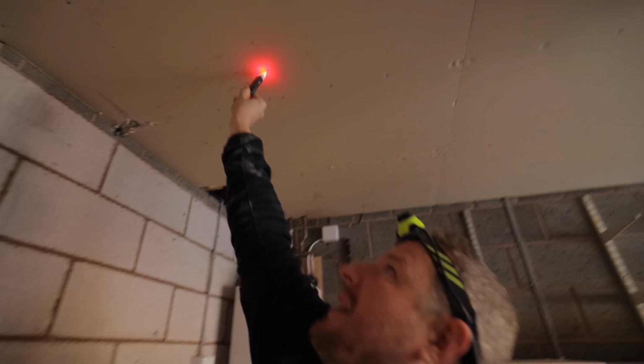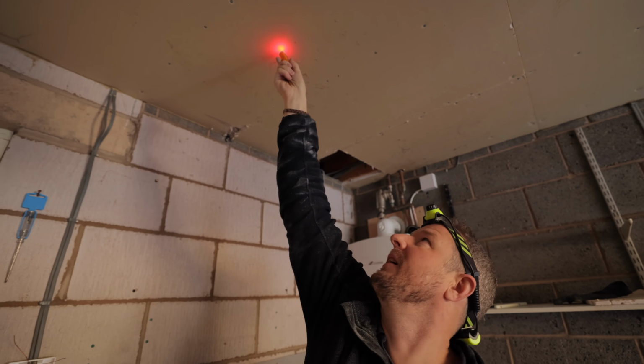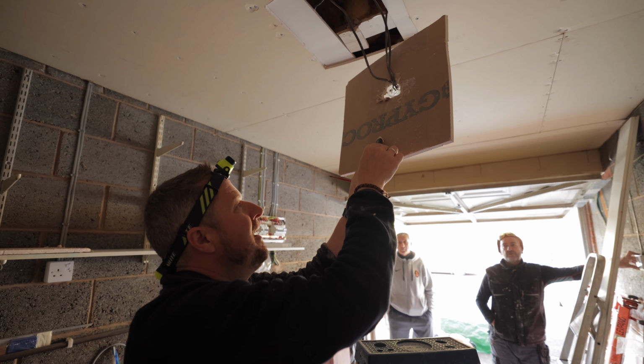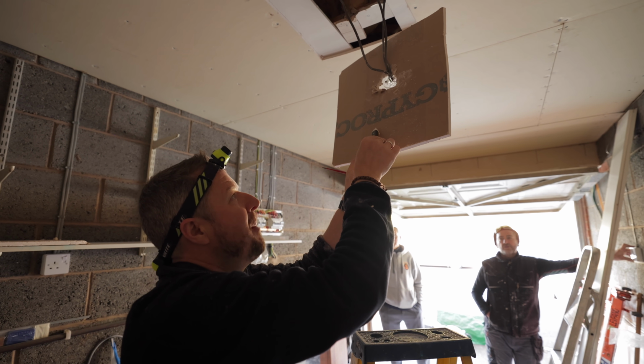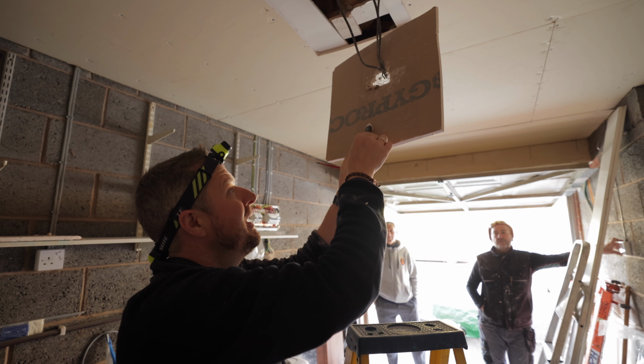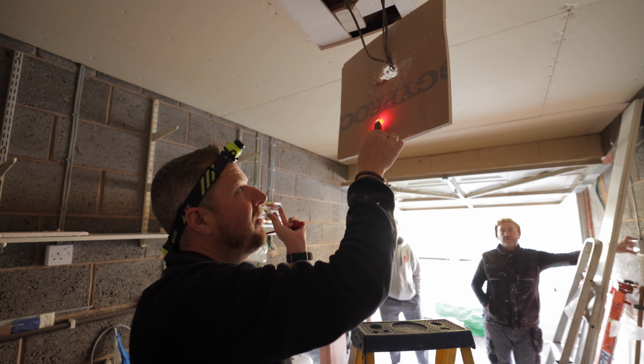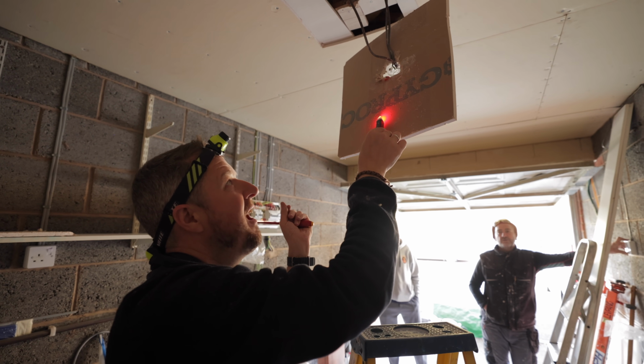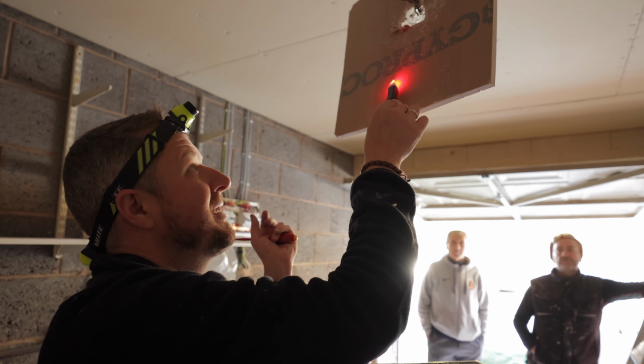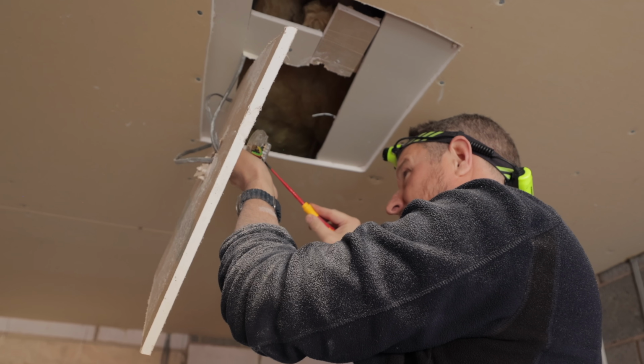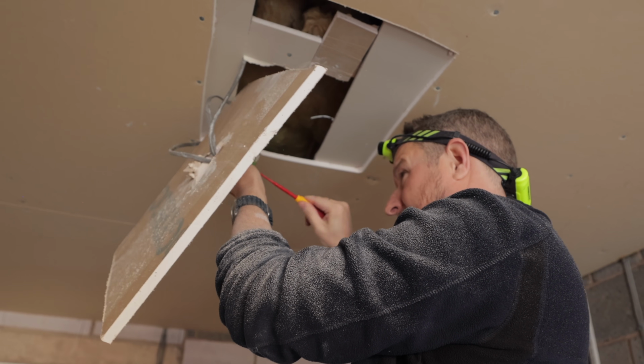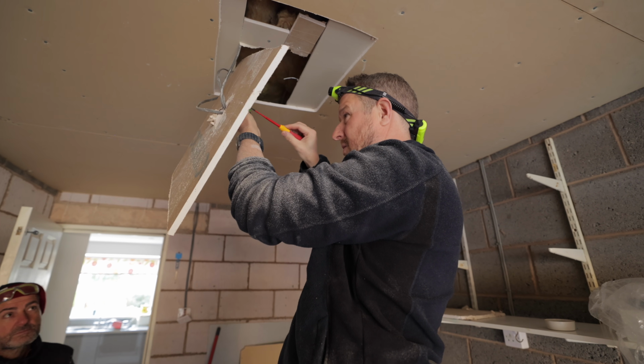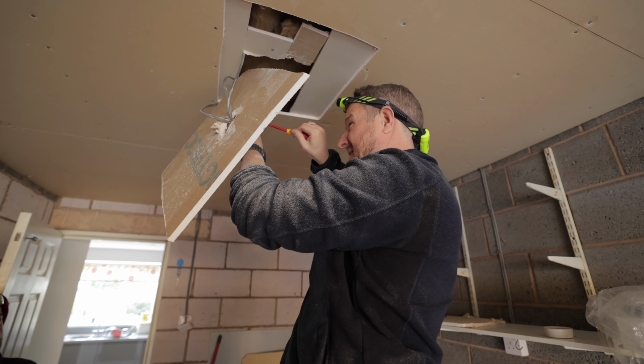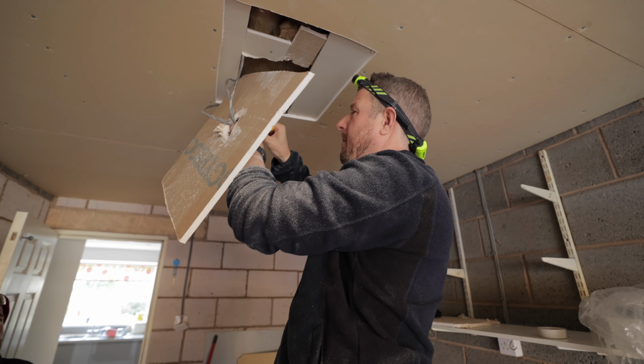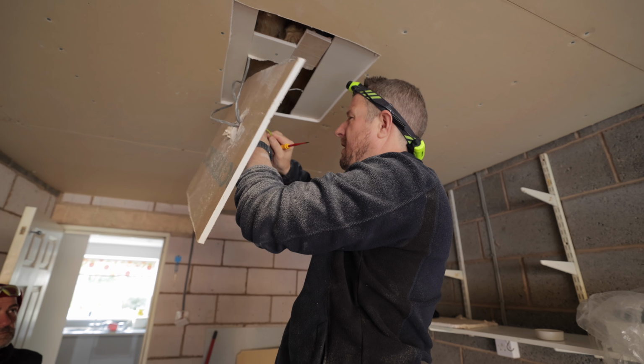Ah, look at that. Main ceiling. Oh no, main ceiling is still doing it. When I touch it, I'm earthing it out and the voltage is dropping. And when I let go, the voltage is increasing just enough. It just literally makes no sense. So it is definitely coming from this lighting circuit. The only logical conclusion is there has to be some kind of damage to this cable, but I just don't understand why it's not showing up.